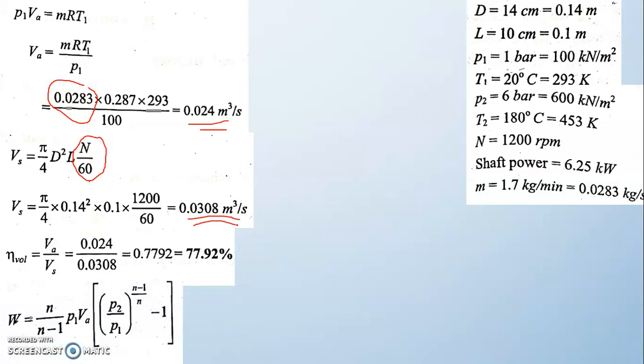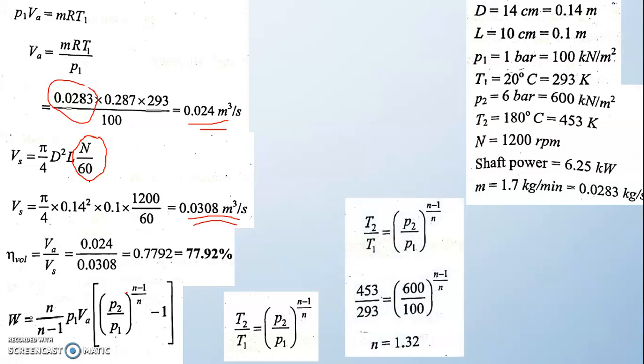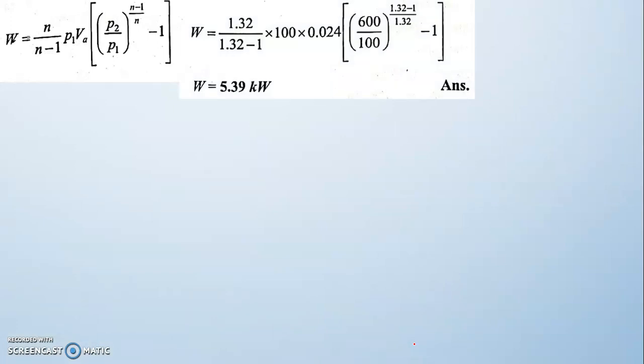For indicated power, we use [n/(n−1)] · P1 · VA · [(P2/P1)^((n−1)/n) − 1]. P1 is given, VA = 0.024, and P2/P1 are known. To find n, from T2/T1 = (P2/P1)^((n−1)/n): substituting 453/293 = (600/100)^((n−1)/n), taking log on both sides gives n = 1.32. Substituting n = 1.32 into the indicated power equation gives indicated power = 5.39 kW.